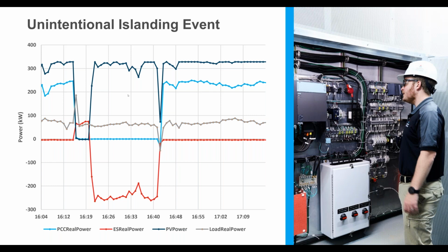Next is an unintentional islanding event that was experienced. This occurred third quarter 2018. What happened here is that upstream of the smart homes, there was a fault that caused the PCC real power, that is the main recloser, to open. As soon as that opened, the microgrid picked up the load immediately and powered the smart homes for 30 minutes until the power control center operator resynchronized the smart homes. Here, the microgrid picked up the load and resynchronized with the grid seamlessly. The homeowners did not see any power blip.